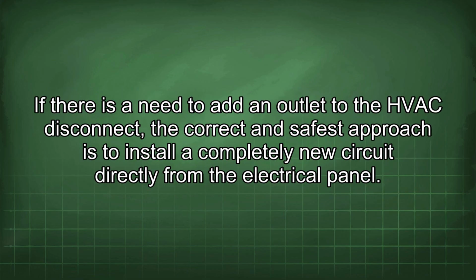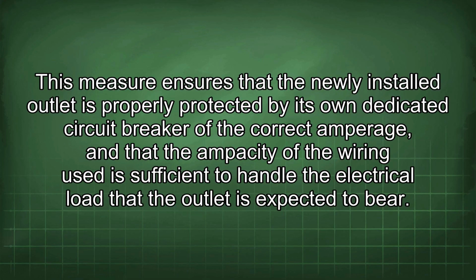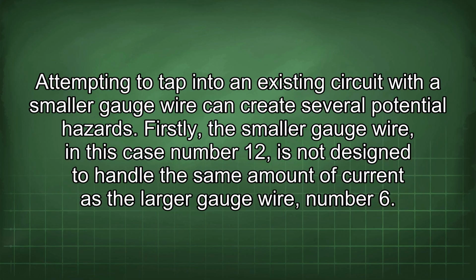If there is a need to add an outlet to the HVAC disconnect, the correct and safest approach is to install a completely new circuit directly from the electrical panel. This measure ensures that the newly installed outlet is properly protected by its own dedicated circuit breaker of the correct amperage, and that the ampacity of the wiring used is sufficient to handle the electrical load that the outlet is expected to bear. Attempting to tap into an existing circuit with a smaller gauge wire can create several potential hazards.